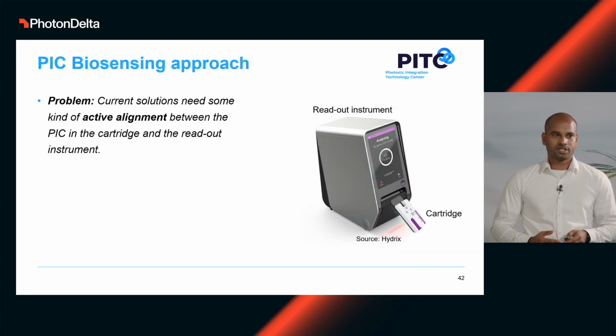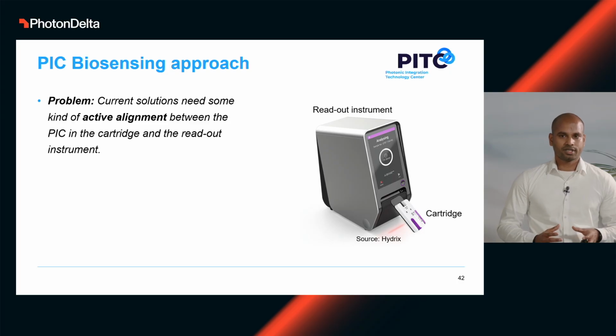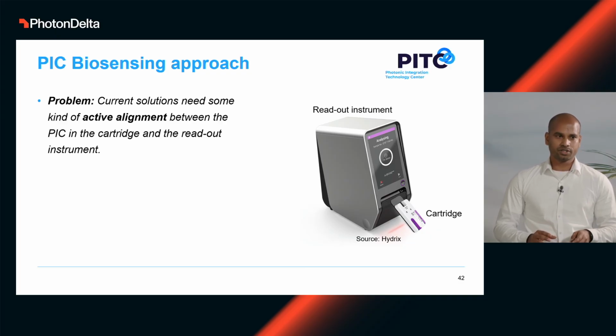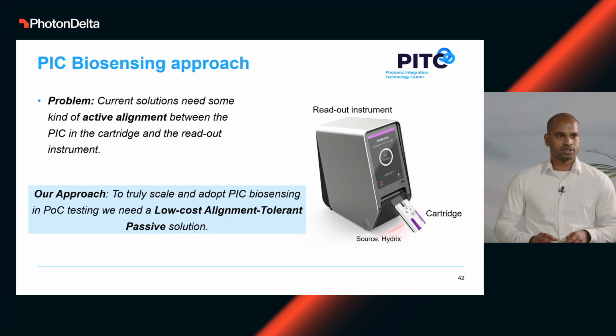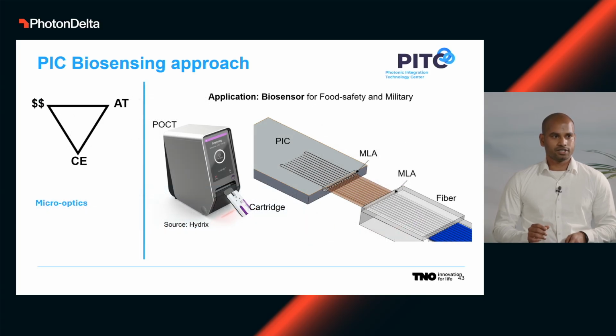Now, coming back to the biosensing approach, if you look at the current market with biosensors, there is always some kind of active alignment between the PIC in the cartridge and the optical unit in the readout instrument. Our approach is to completely eliminate this active alignment, and we believe that to truly scale and adopt biosensing in POC testing, we need a low-cost and alignment-tolerant passive solution. That's what we looked at in the benchmark, and we see that to have a low-cost and alignment-tolerant solution with a nominal coupling efficiency, micro-optics is the best solution.